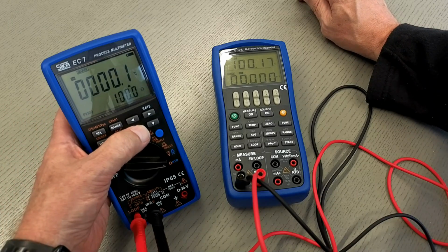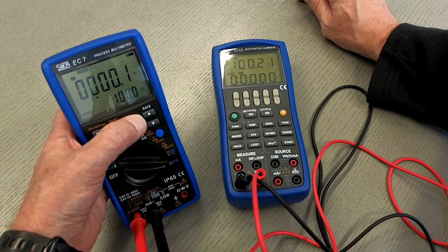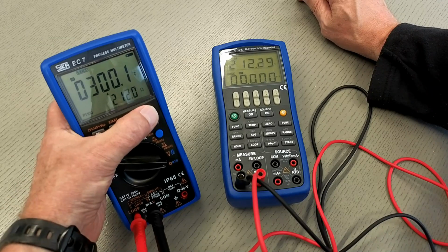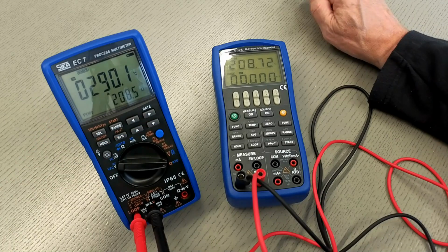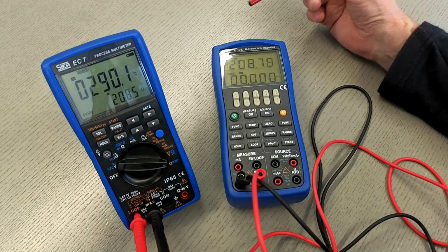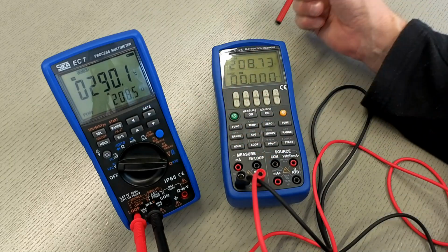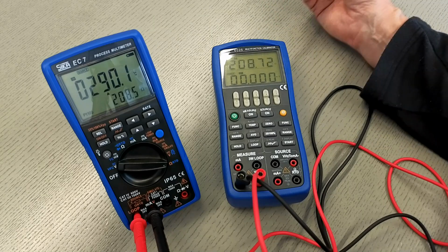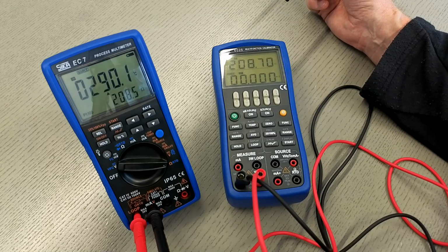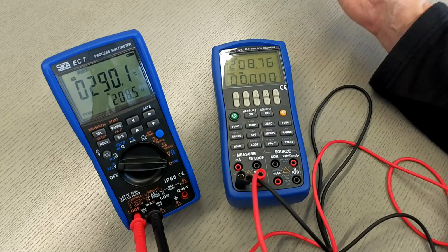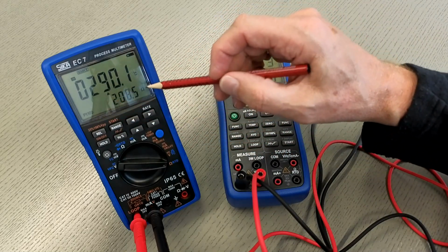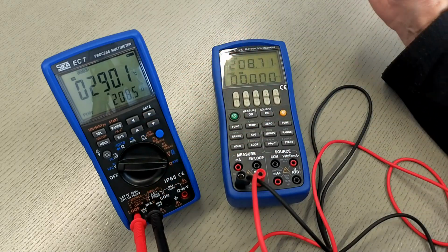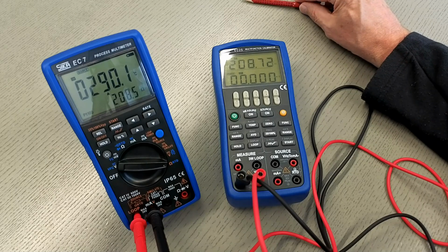And then I can also increase the temperature. I go to the selector switch and, for example, 290.1 degrees Celsius, 208.5 ohms. On my indicator I see 208.7 ohms. So everything is in the specified range. A Pt100, temperature and ohm generated, and the signal is coming out on terminal number 1 and terminal number 2. Yep, that's all.